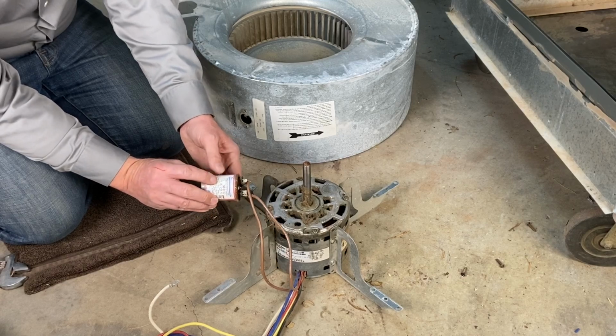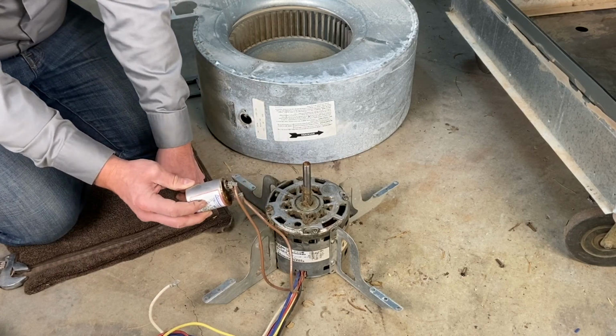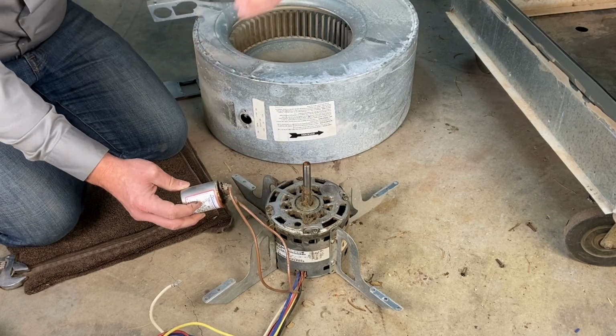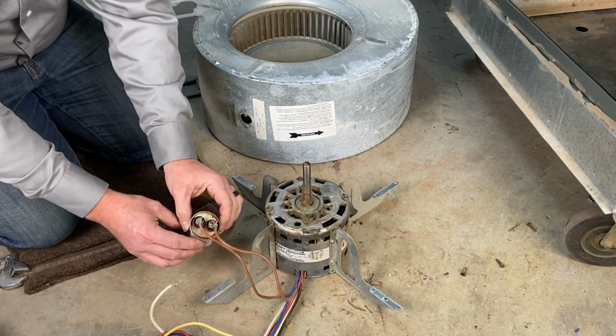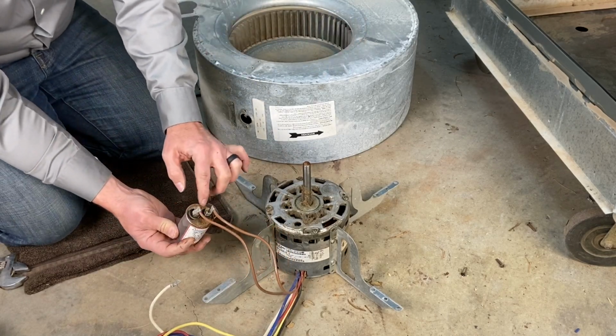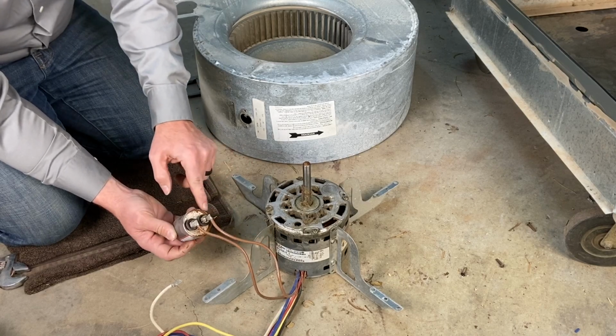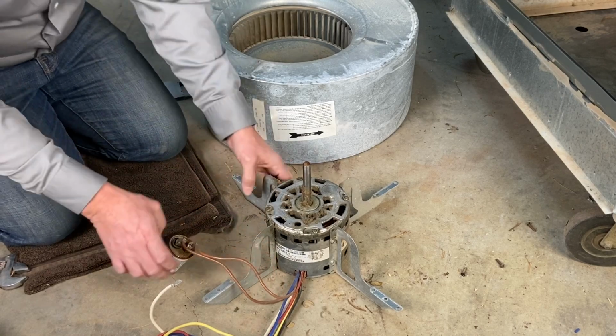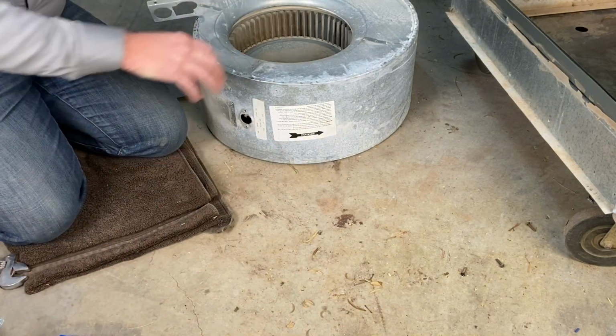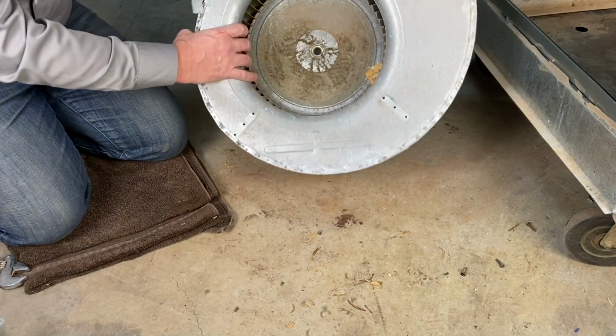We also want to make sure we use a 370 or we could use a 440. The capacitor can be larger but never smaller. These are things that we want to check. Also, if we notice there's a significant amount of rust here, we'd want to note that on the invoice as well. So what we're going to do is move this motor out of the way. And we're going to take a look at this blower wheel and housing.